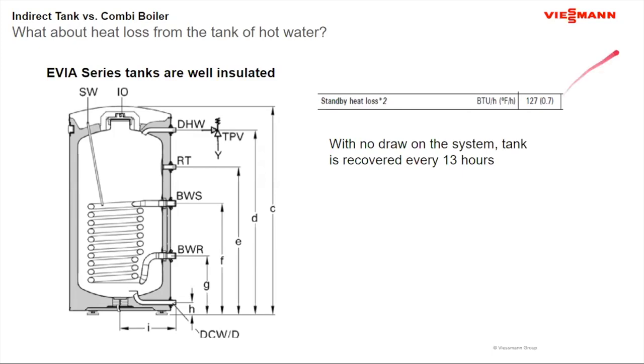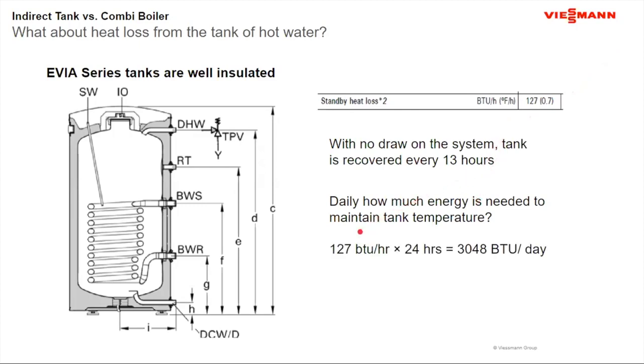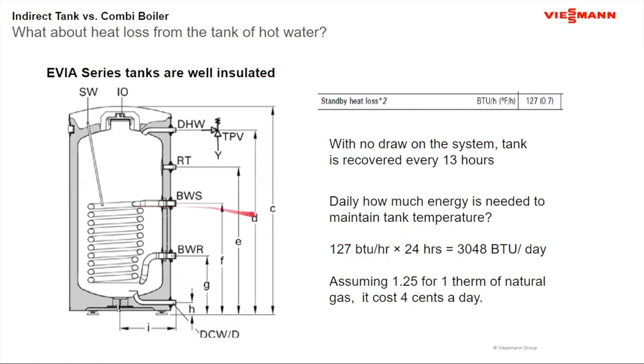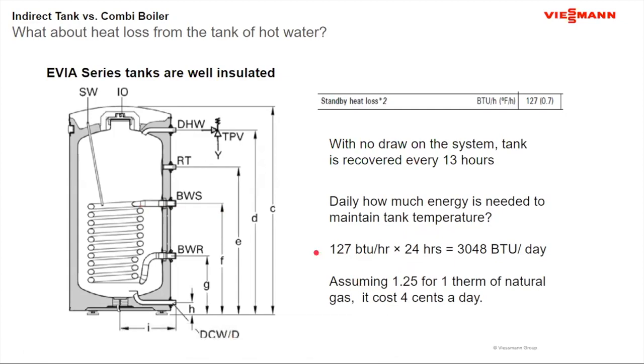Now, if I look at recovering this 127 BTUs per hour, I look at the energy that's needed. If I take 127 BTUs, I multiply that by 24 hours, the tank is wasting 3,048 BTUs per day. Okay, now let's take that and change it to something more meaningful. Let's talk money. So assuming that a therm of natural gas costs a buck and a quarter, to maintain that tank hot 24 hours a day costs about 4 cents a day. So it's very minimal, the amount of energy that's being wasted because of the level of insulation.